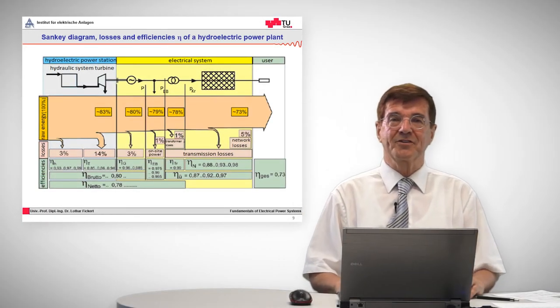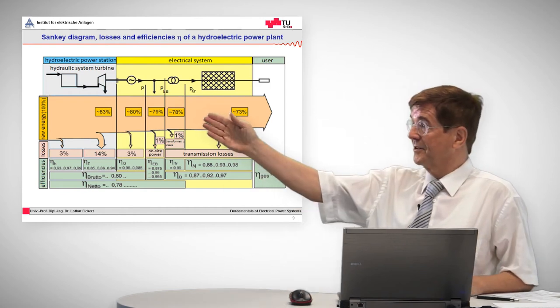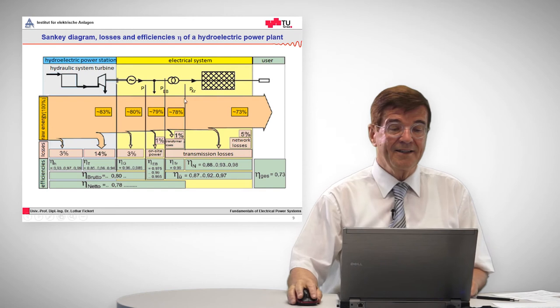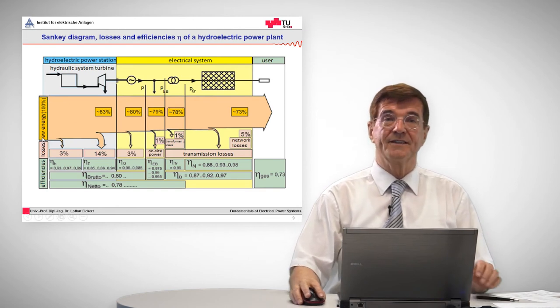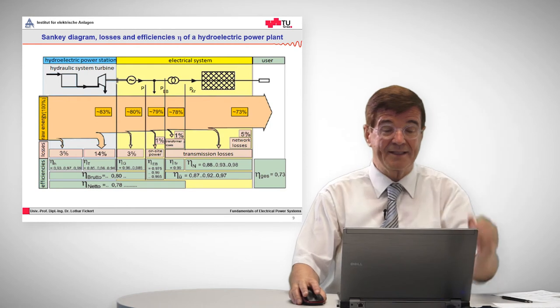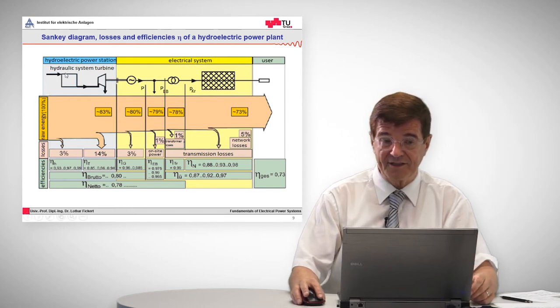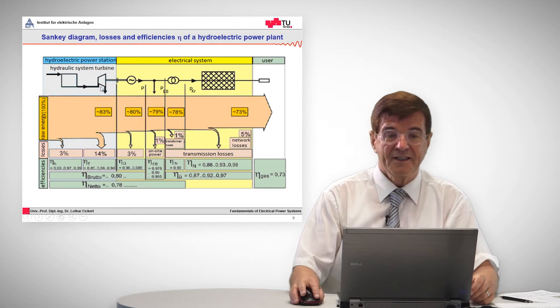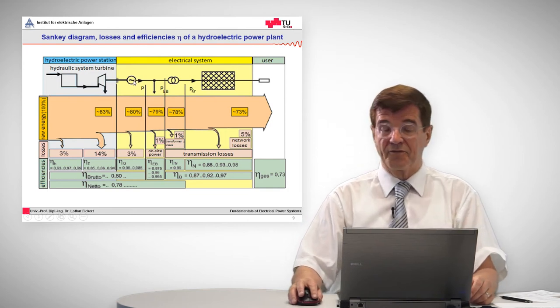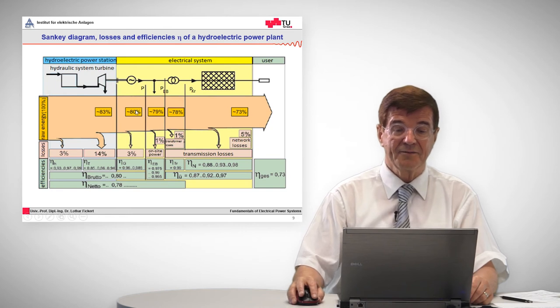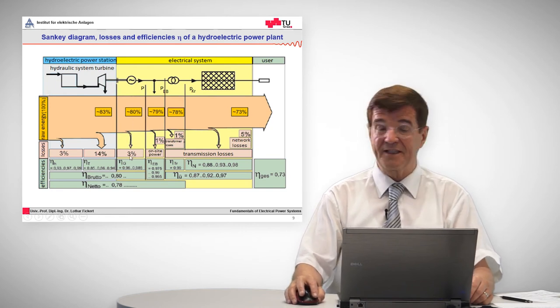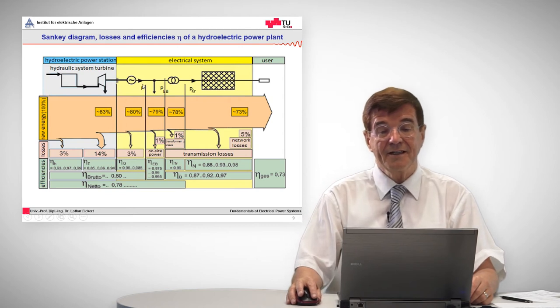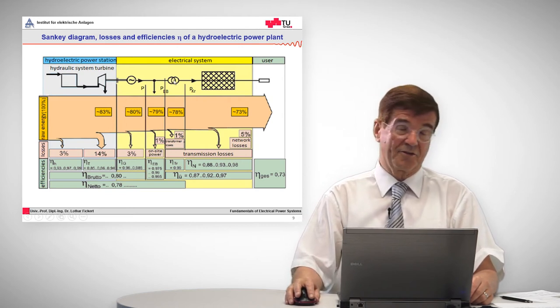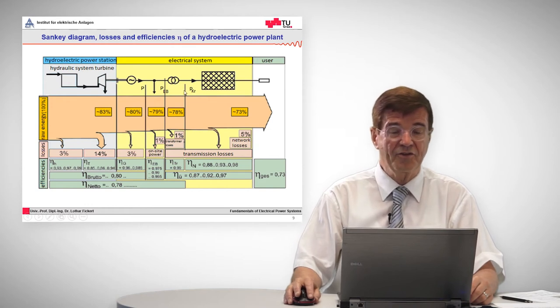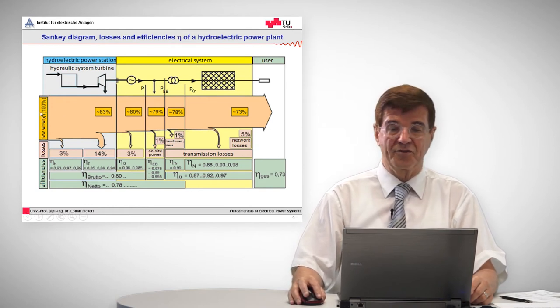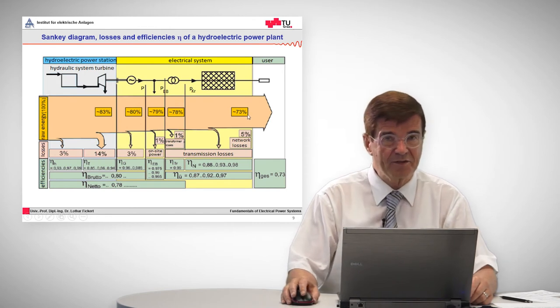We are also familiar with the concept of the Sankey diagram, which you can see here on the right side, which means that the whole raw energy of the water, that is the static energy which is in the upper basin, is converted through the hydraulic system with certain losses into the turbine. From there, it is converted in the generator with a high efficiency of 97% into electrical energy. And then it is put through the so-called station transformer into the electric grid. So the overall efficiency from the source to the sink is roughly 73%.